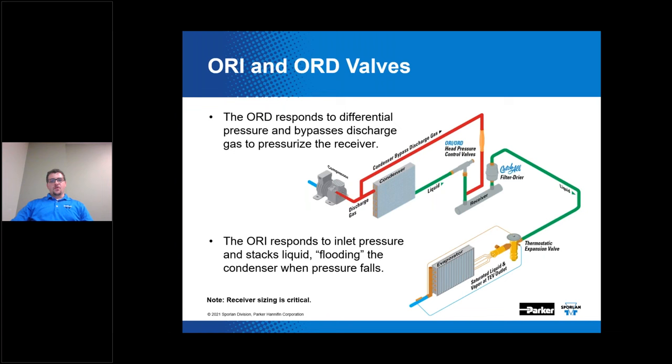Now we move on to flooding of the condenser. Condenser flooding is a different method of head pressure control — it also reduces the effective area of the condenser but accomplishes that differently than splitting the condenser. This is one of the two-valve versions of head pressure control: the ORI and ORD combination. The ORI is frequently referred to as the condenser holdback valve, located in the drop leg of the condenser. ORI stands for Open on Rise of Inlet Pressure.